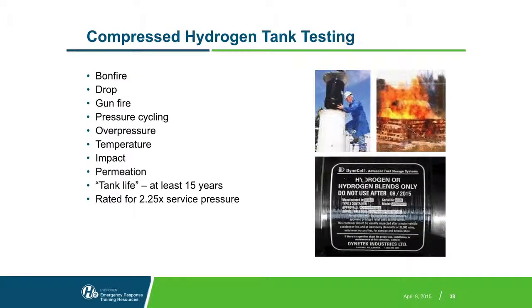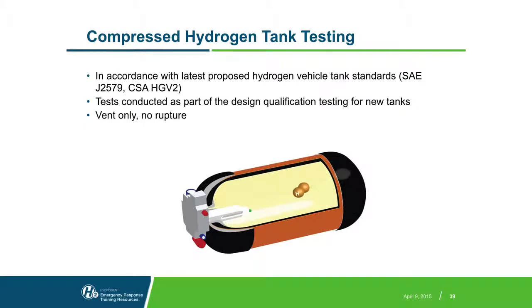In terms of the qualification for these tanks, and this goes for the ones that are in the unit, vehicles, etc., they do go through a series of rigorous testing per batch to qualify them for a lifetime of at least 15 years. And they have a safety rating of a minimum 2.25 times the service pressure. So while these tanks are being used at 5,000 psi service pressure, they can actually withstand much higher pressures. These tanks are designed to NGV2, which is also an acceptable vehicle tank standard.